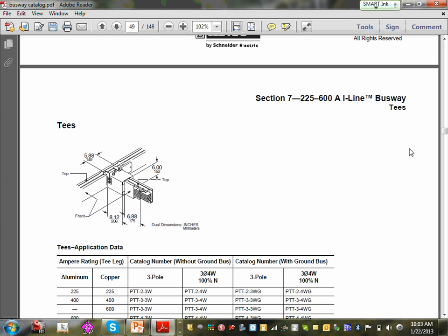You were saying something about the bigger bus, once you get in the room, then you have to split. What the requirement right now is to bring the feeder, and then you have to have a circuit breaker and feed sections. Oh, okay. So you're not teeing off and then running. The feeder will be like, I think, a 1,000 amp feeder, and then you tap 225 this, 225 that, and keep tapping into it. There's one behind you right here. You see that, yellow? The yellow is 225, the blue is the feeder, I think 1,000 amp or something. You're still gonna employ T's here. Yeah, for the feeder, yep.